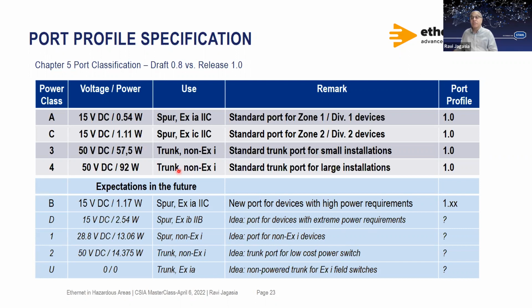You could run this in zone 2, div 2, and you will be able to drive more power into the hazardous area. We expect some more designs to be coming up, more options of the different power classes to be coming up, and expect that maybe in a year down the way, the first ones when the 1.0 versions are coming in, and then you could be even looking for non-Ex i devices or trunks for low-cost power switches. A lot of variants are on the roadmap, but we, the Ethernet-APL organization, will be evaluating the demand and the adoption as it goes forward.